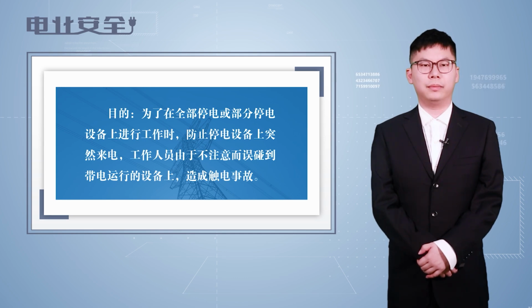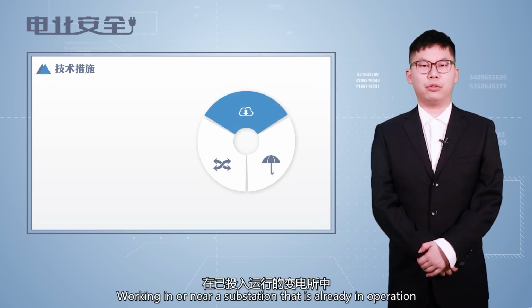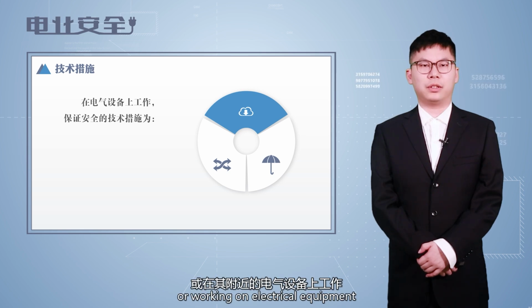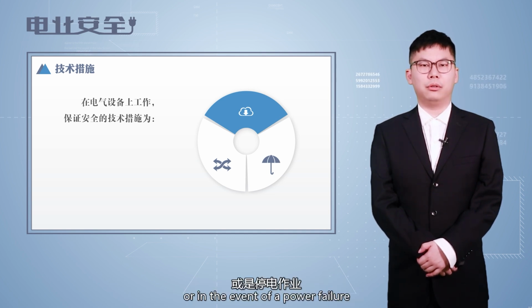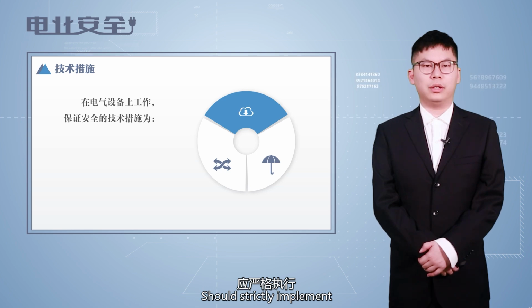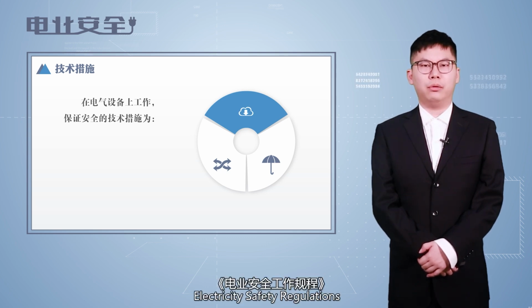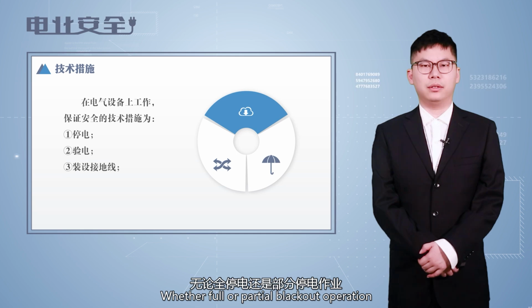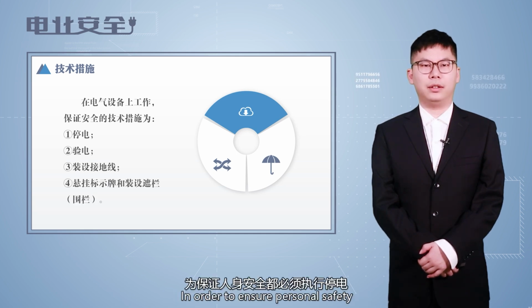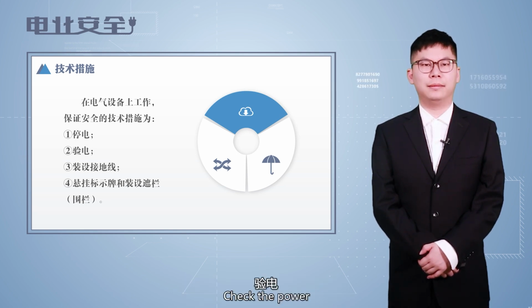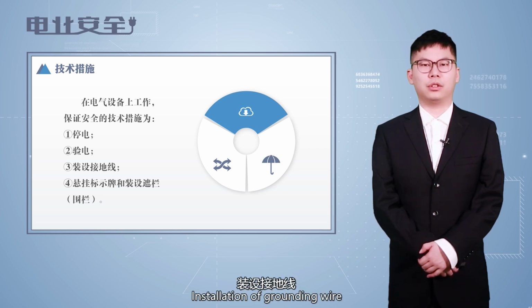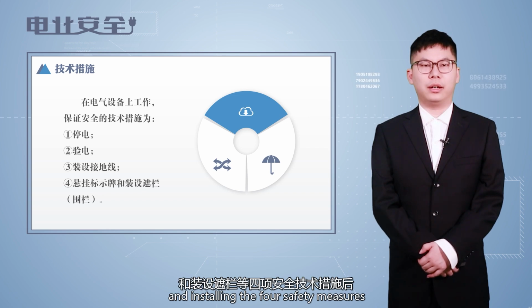shock accidents. Working in or near a substation that is already in operation, or working on electrical equipment in the vicinity of electrical equipment, or in the event of a power failure, should strictly implement electricity safety regulations, fulfill the power failure ticket system, whether full or partial blackout operation. In order to ensure personal safety, must carry out blackout, check the power, installation of grounding wire, hanging signs, and installing the four safety measures such as shielding fence.